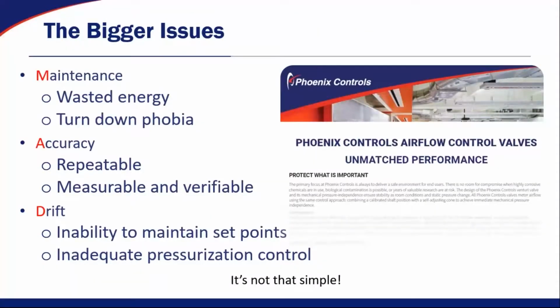Now, I mentioned maintenance, accuracy, and drift when it comes to VAV boxes, and these are really the big key items that we talk about. So what does maintenance mean? Well, it's wasted energy and something called turndown phobia, which basically means when I set my rooms from occupied mode to unoccupied mode, there is a chance that my pressurization could switch. And in that particular case, I can't have pressurization switch when you think about operating rooms or really critical environments with patients or things like that. So instead of turning down the space to save energy, they just leave the building running at full occupancy. Again, in an operating room, take 15 to 20, 25 air changes per hour, where they could turn it all the way down to 4 or 6 or 8 air changes per hour and save all that money when they're not occupied. They tend to just leave them running.